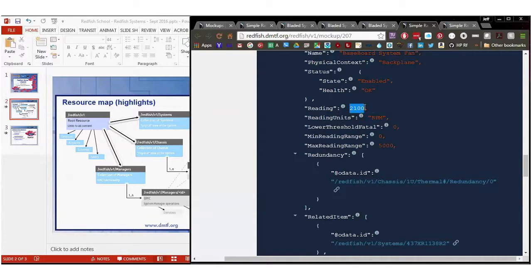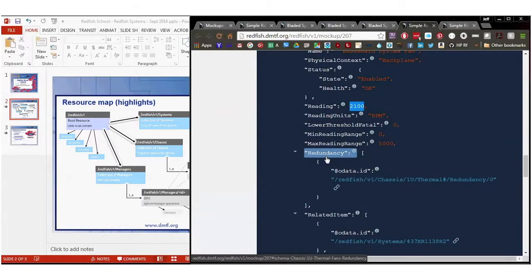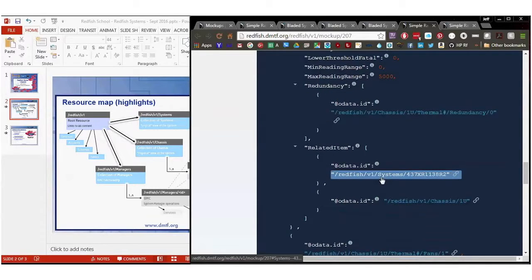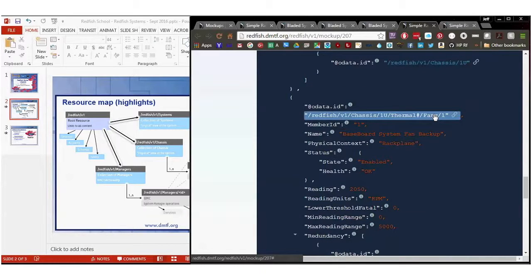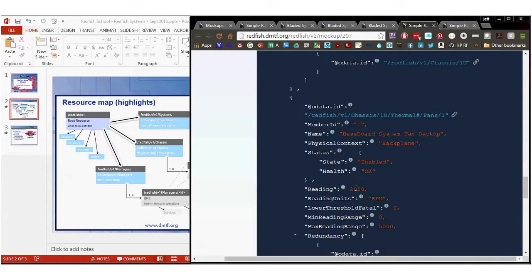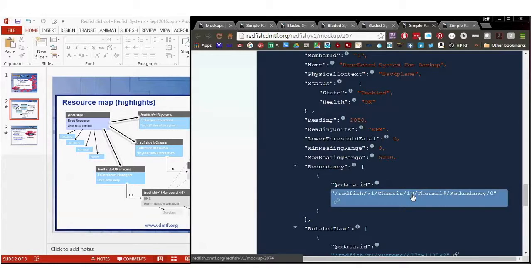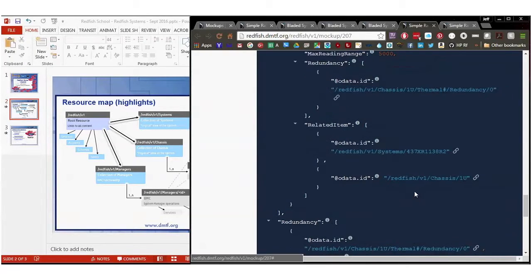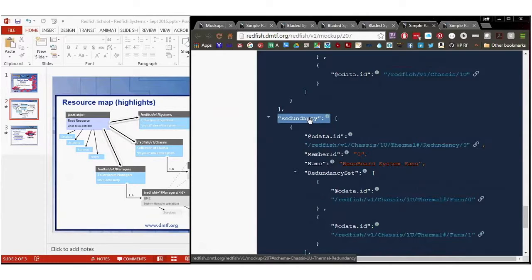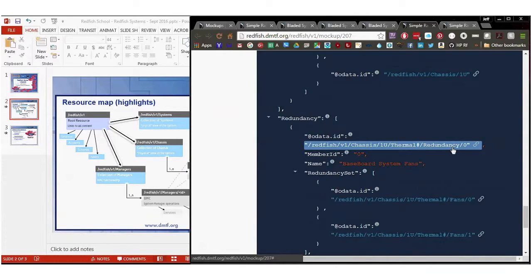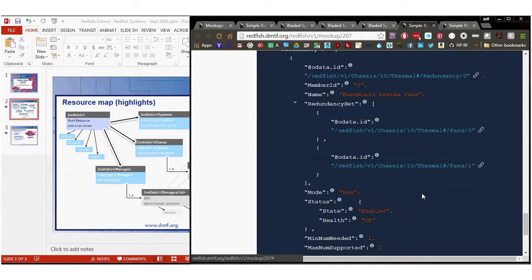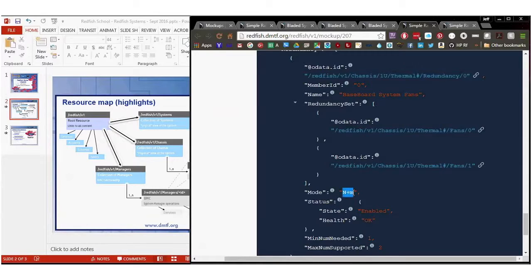It's a redundant fan. So it's got redundancy object zero. It tells you what other fans are associated with this one, and this one is related to system, this particular system ID. Here's another fan, and it's running a little bit slower, and it's also in a redundancy set, and its related item is the same system. And here's my redundancy set down here, which is the third collection. I look for redundancy zero in it, and I find my redundancy set is fans zero and one. And of course, there's a status associated with it, as well as a mode that shows my redundancy mode. This one is an N plus M, so I need one plus one. So I really only need one.